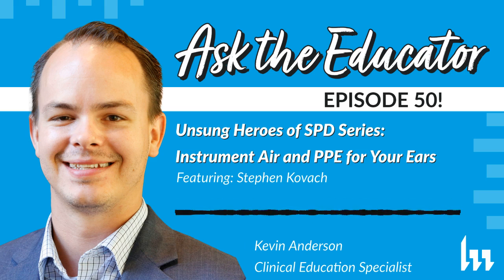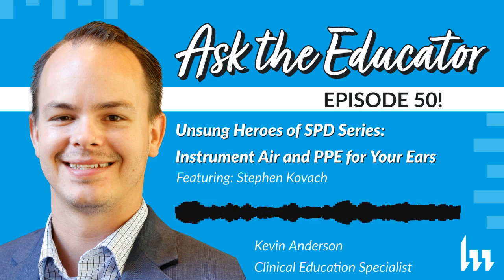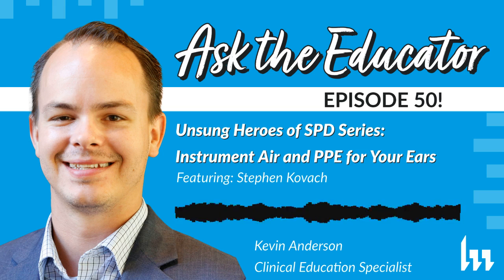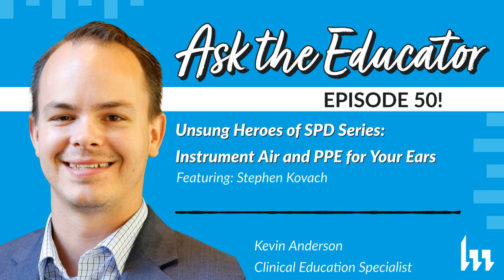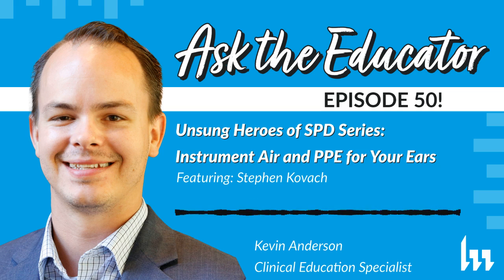So the air you should be using, unless the manufacturer's IFU specifies differently, is instrument air to remove excess moisture from the cleaning and rinsing. And you also need it on the clean side. When we're talking about the water gun, you don't really have a water gun on both sides, but you're using air to make sure a lumen or a suction channel is patent, that nothing's there. The force of the air can push things out, but it's also used for drying. And there's a lot of reasons for that. Some of the low temperature sterilization systems require things to be dry, so there had to be a definition for it. And let me ask you this, Kevin, did you have air on the clean side in your department?